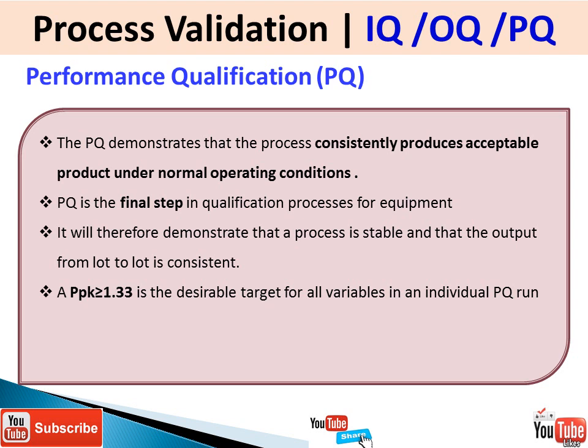Performance qualification demonstrates that the process consistently produces acceptable product under normal operating conditions. PQ is the final step in the qualification process for equipment. It demonstrates that the process is stable and that the output from each lot is consistent. Here we look at Ppk values, which should be greater than or equal to 1.33, equivalent to a four-sigma level.